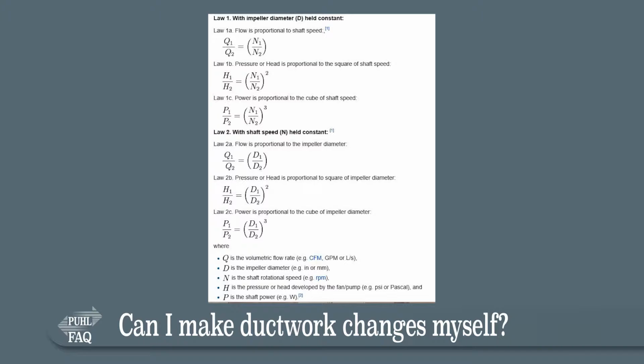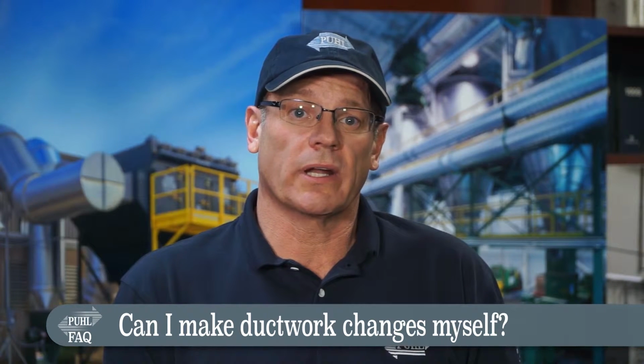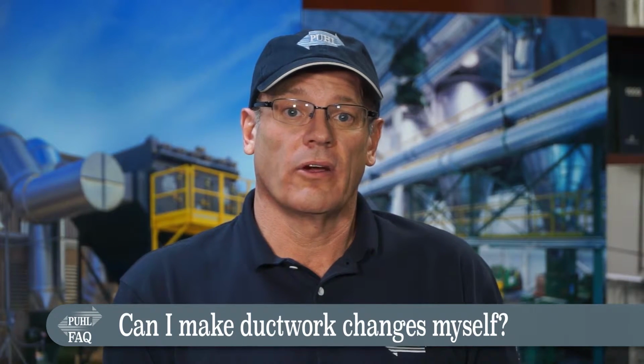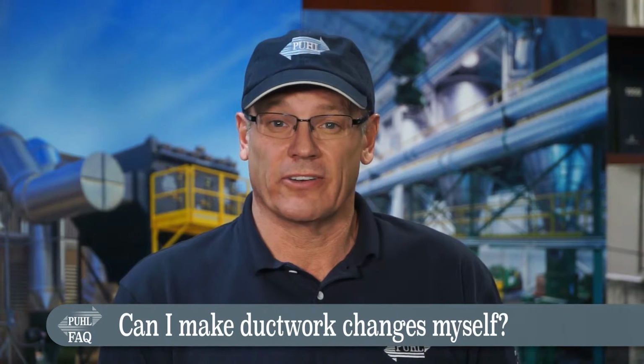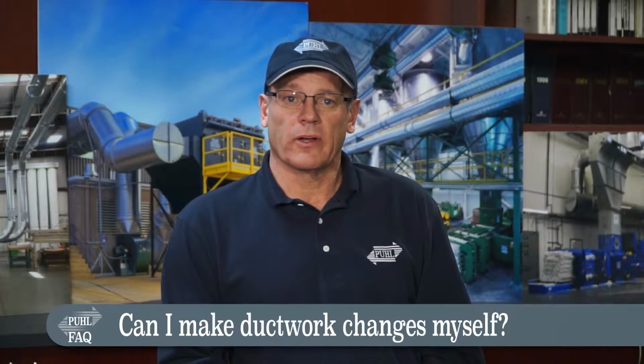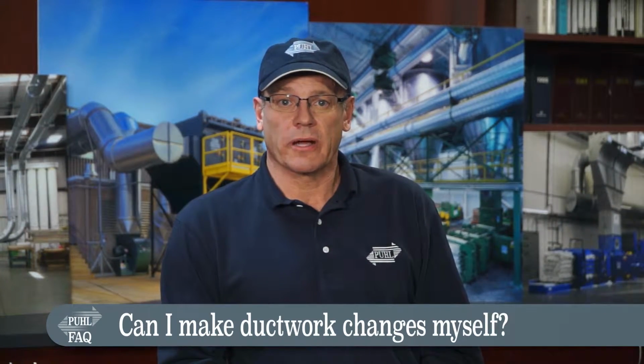So if you miss the ductwork design by only a few feet, and you have to speed the blower up just 50 RPMs, you can be in effect using a lot more electricity all year, every year, than you saved in the beginning. In the average electric cost per kilowatt hour state in the USA, 1 horsepower costs about $500 per year. If you're thinking about calling your local HVAC contractor to do the job, you may want to think again.